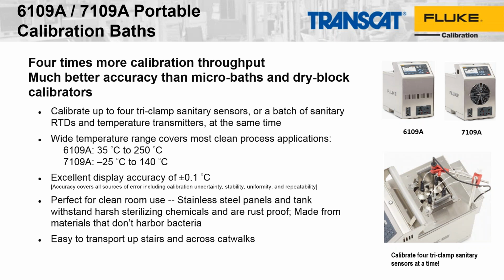The reason we're saying that they can calibrate 4 times more throughput than other macro baths or the micro bath line is because the tank size will accommodate 4 times. And you can see a picture there of the 4 sensors installed in there with a reference thermometer placed in the center of the bath. The temperature range for the 6109A is 35 to 250, and then 7109A from -25 to 140. And the accuracy of the temperature displayed on the instrument is 0.1 degrees C.